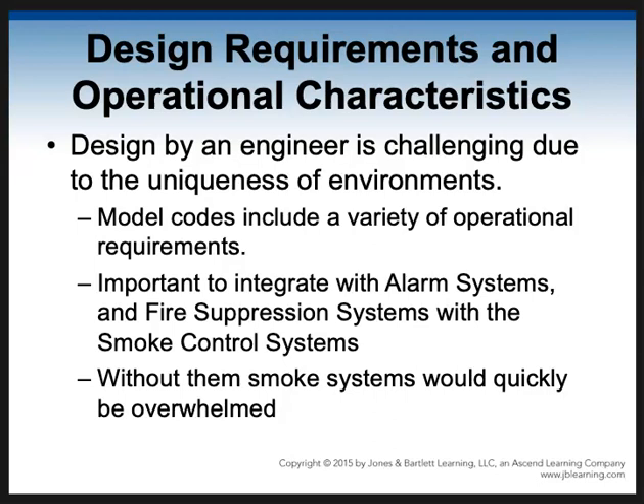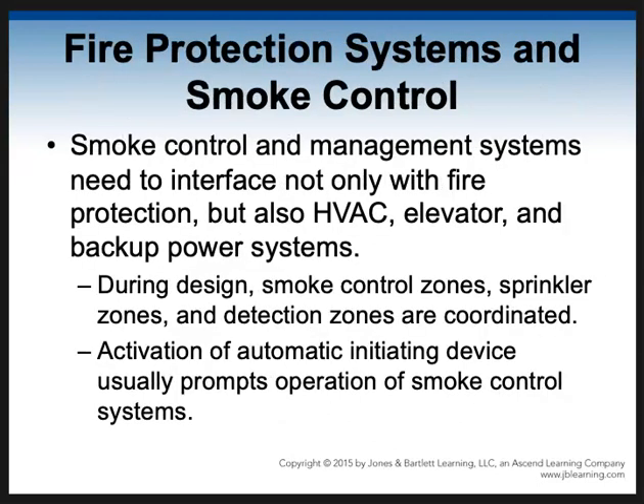And the codes give a lot of operational requirements. The standards help, but when it comes right down to it, you need an engineer who figures out the best way to do it. And of course, it's very important to integrate these systems with the alarms, with the fire suppression, and the smoke control all working together. So without those other systems, the smoke control systems would get overwhelmed quite quickly. So when they're going to design them along with not only our fire protection systems, but our HVAC, our elevators, our backup power systems, all of these.